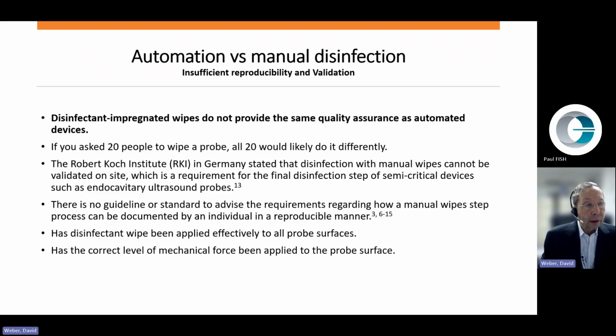Let's continue talking about automation versus manual disinfection. Disinfectant impregnated wipes do not provide the same quality assurance as automated devices. If you ask 20 people to wipe a probe, likely all 20 would do it differently. The Robert Koch Institute in Germany stated that disinfection with manual wipes cannot be validated on site, which is a requirement for the final disinfection step of semi-critical devices such as endocavity ultrasound probes.